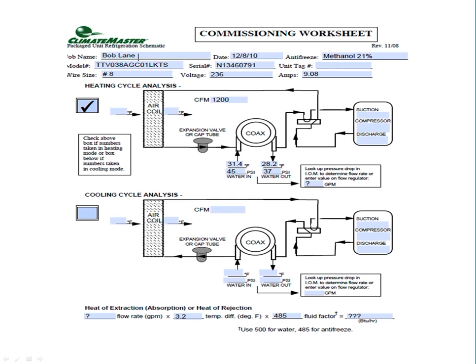Our next example here is an 038 2-speed. This one has a more appropriate methanol concentration of about 21%. This is in the heating mode, and let's see where this one takes us. So we have the 1200 CFM, that's good, 400 CFM per ton. We have an entering fluid temperature of 31.4. It is exiting at 28.2, so that's about a 3-degree difference.